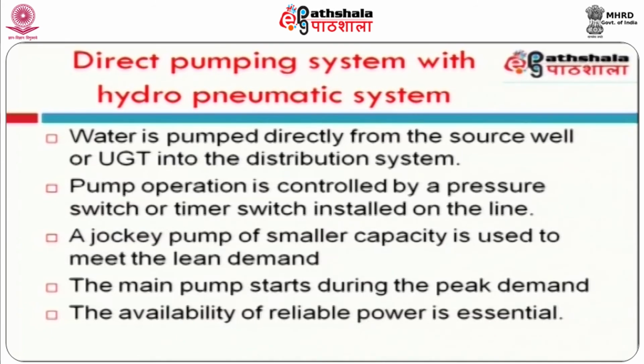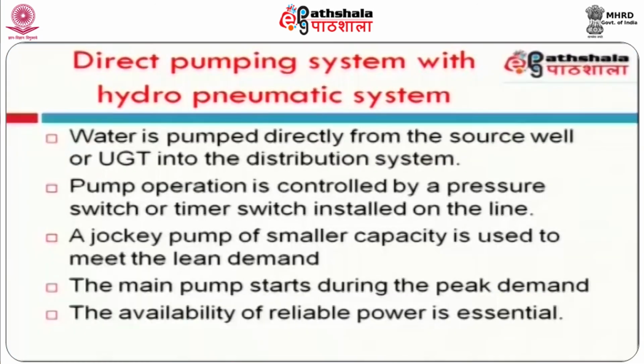You need not divide the entire stories into different zones. We can pump directly to all the stories. The pump operation is controlled by a pressure switch or timer switch installed in the line. So whenever there is a drop in the pressure or demand in the building, it triggers the pump to operate. The pump will automatically switch on and start supply.